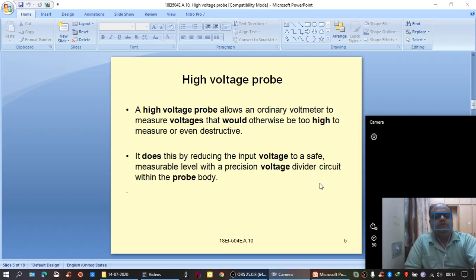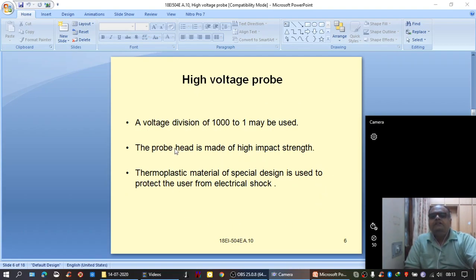That is, within the probe body itself, a voltage divider network is placed. A voltage division of 1000 to 1 may be used. That means every 1000 volts can be converted into 1 volt by using the potential divider network employed inside the probe, using the 1000 to 1 ratio. The probe head is made of high impact strength. High impact strength, what does it mean?